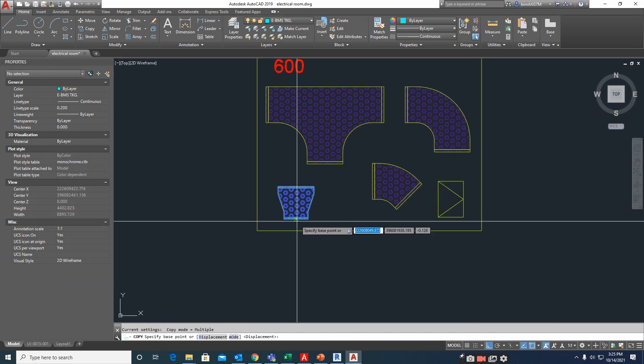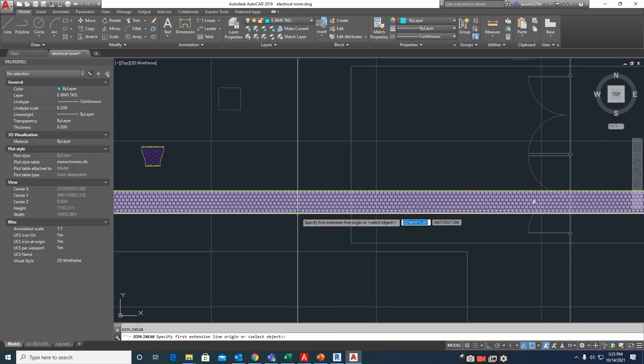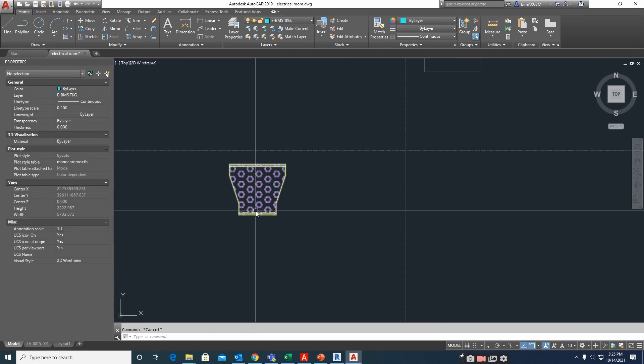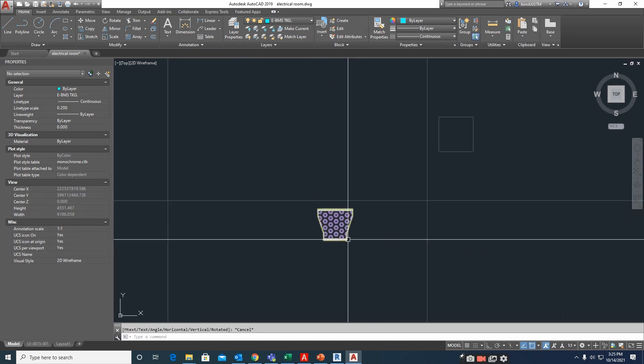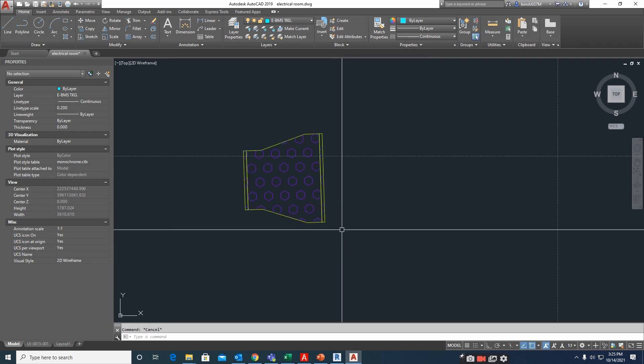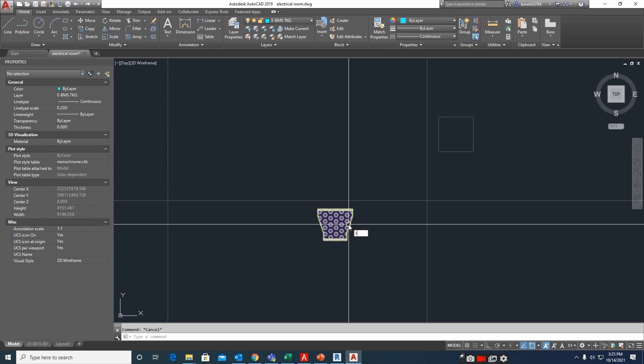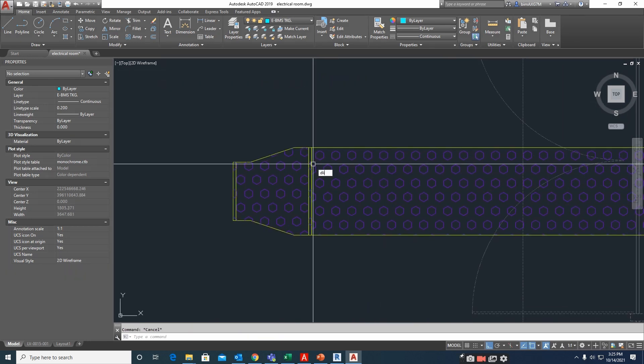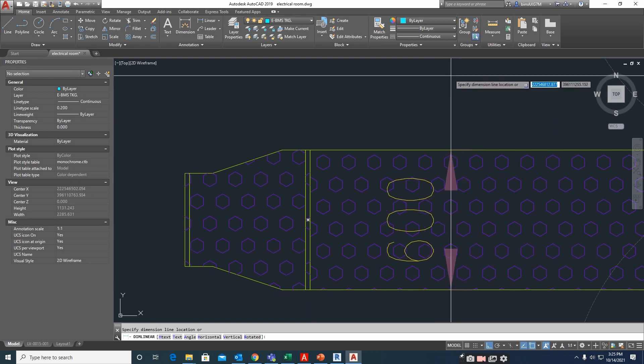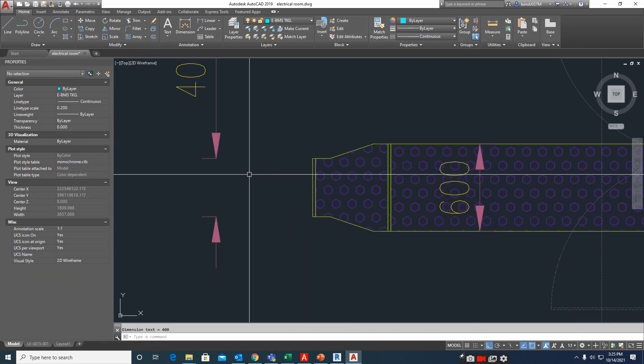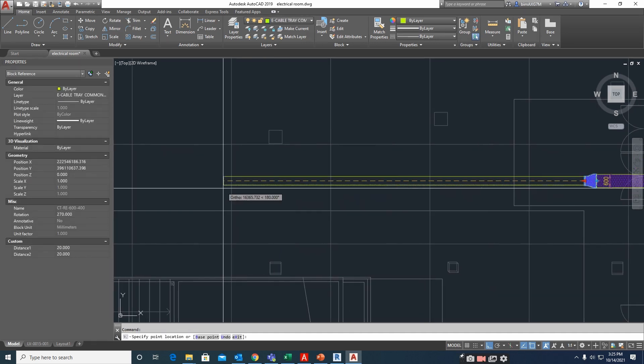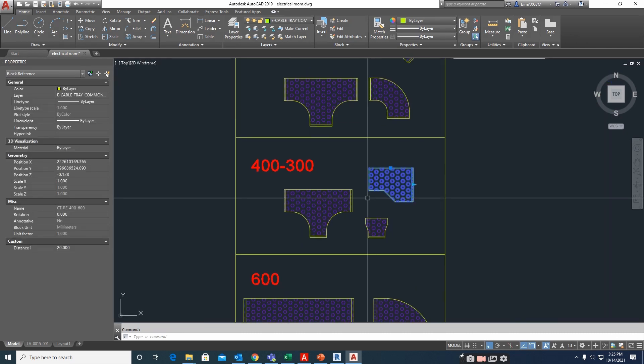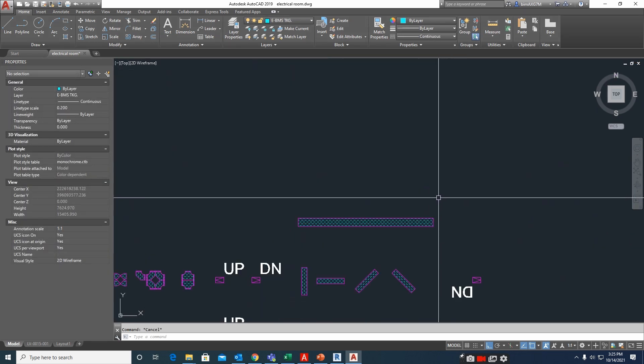Next, if you have a reducer — you need to reduce the cable tray — up to here it is 600, and from here you need a 400 cable tray. Just pick one center point and place the reducer fitting here. This fitting reduces from 600 to 400. Click here and stretch up to wherever you want — it goes like that. You can make lots of cable trays easily this way.